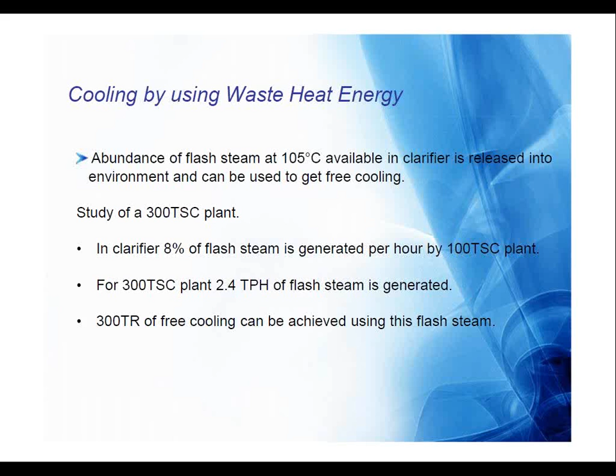On this 2.4 tons of flash, which is coming at around 105 degrees centigrade, we can generate 300 TR equivalent of cooling by using this flash in the vapor absorption system. So the flash which is presently getting dumped into the atmosphere can straight away give you close to 300 TR, considering a 300 TCH plant size, which is a great opportunity for the entire sugar industry, and can be consumed for either air conditioning requirements or even for drying the sugar.